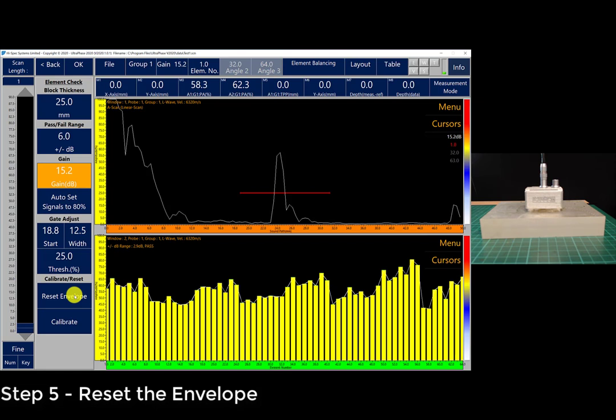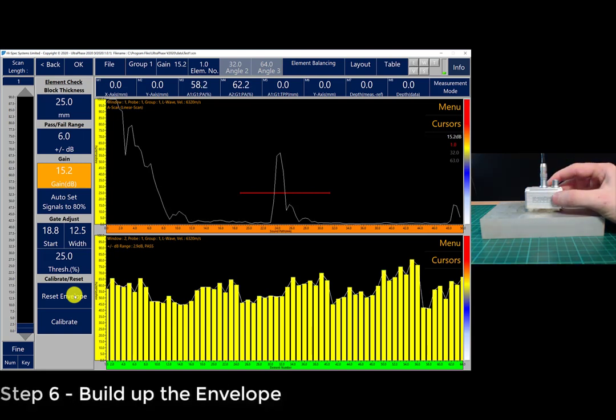Step five would be to reset the envelope in preparation for the actual calibration. Step six would be to build up the envelope by slightly moving the probe back and forward. You may have to press a little bit down on the probe to make sure all the signals are at their peak response.